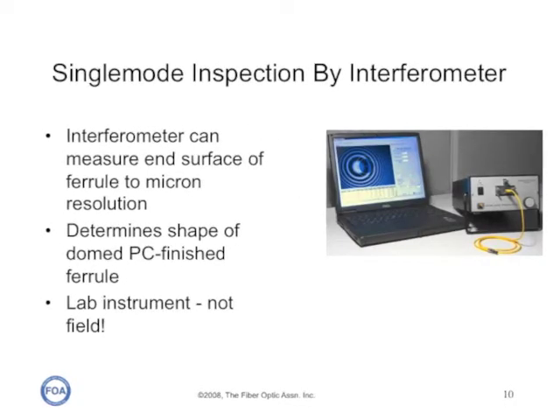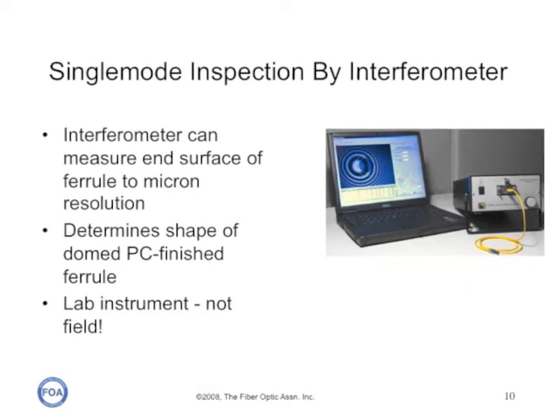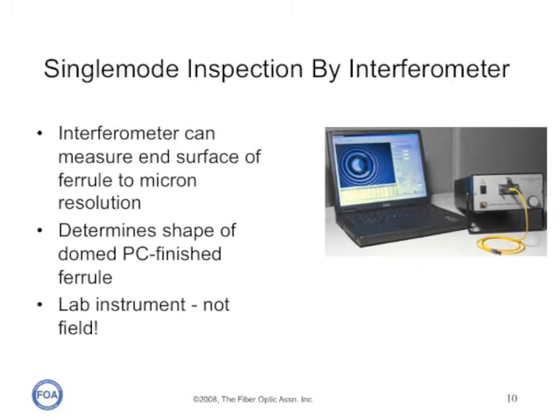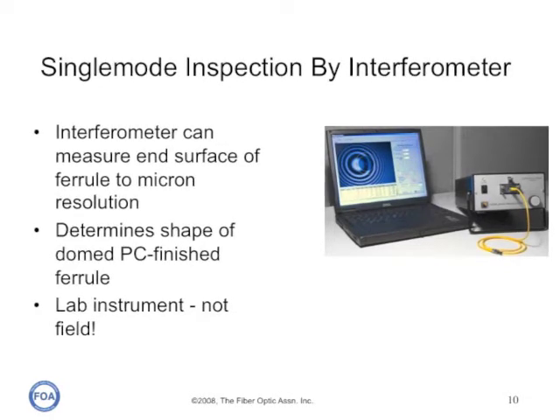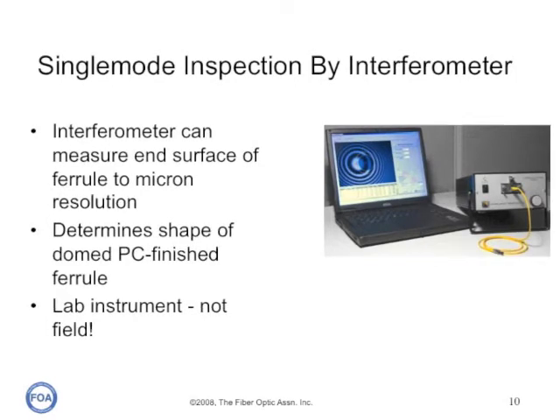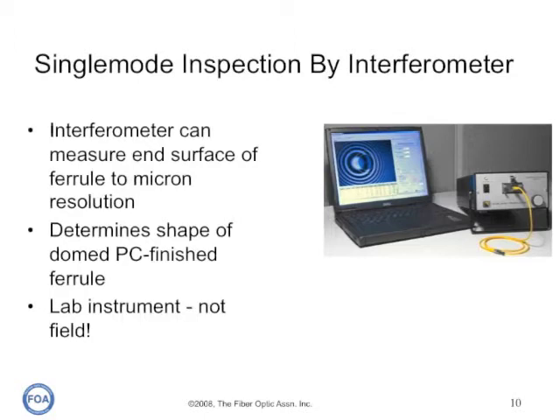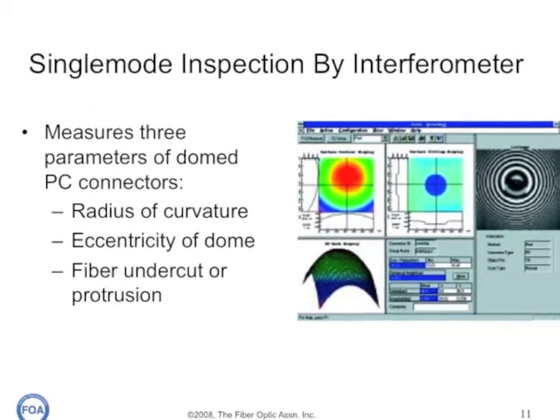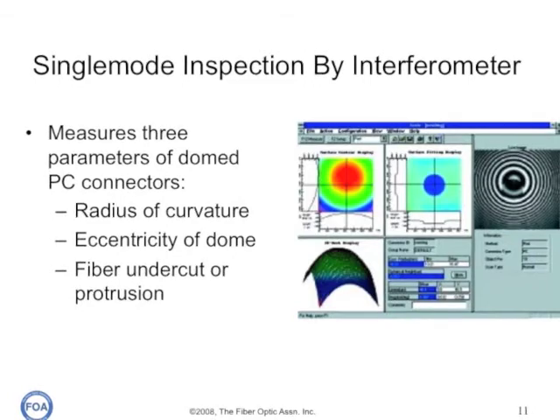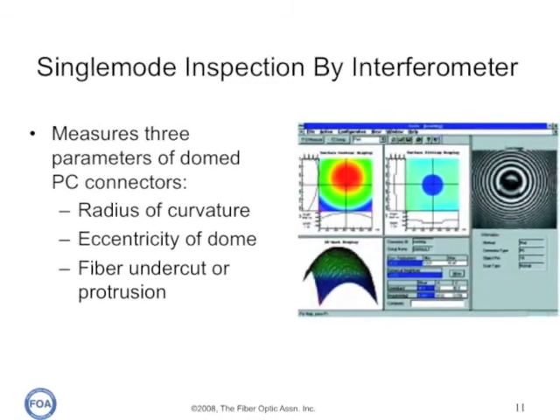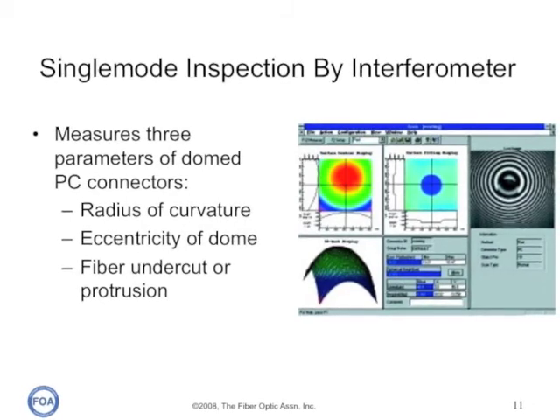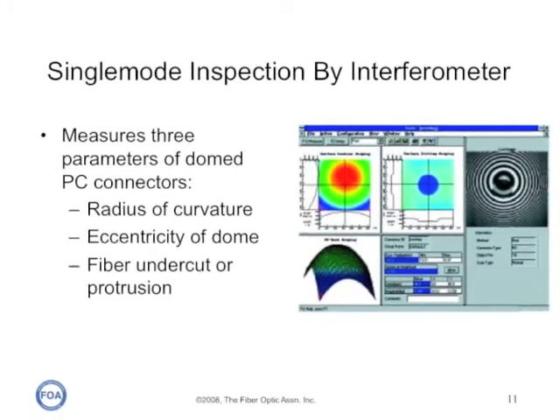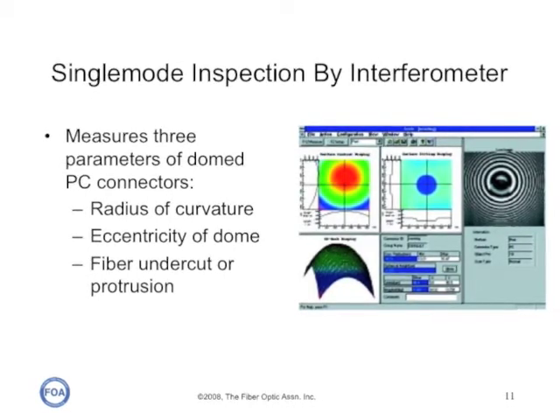On single mode connectors, we do another type of visual inspection using an interferometer. The interferometer can measure the end surface of the connector and actually determine the shape of the PC or physical contact finished dome of the ferrule. Interferometry is only used with single mode connectors generally and it's only a lab instrument, not a field instrument. Interferometers show us three parameters of single mode domed polish connectors: the radius of curvature, the eccentricity of the dome — or whether the dome is centered on the fiber — and whether the fiber has been undercut during the polishing process. It's an extremely sensitive way of determining the quality of single mode connectors.